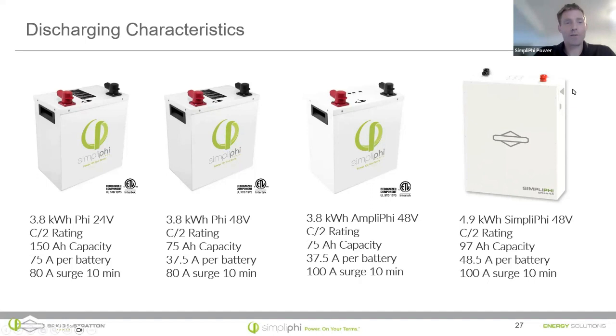Let's talk about discharging the batteries. On the discharge side of things, we can actually surge the batteries, so they're capable of discharging at higher amperages for shorter amounts of time. If I have a battery under standard temperature conditions like room temperature, I can pull 80 amps out of the Phi batteries, so 80 amps out of both the 24 volt and the 48 volt. So a C/2 discharge. If I'm going to do it continuously, I would want to use 75 amps per battery for the 24 volt and 37.5 amps for the 48 volt battery. But if I want to just pull a short amount of current out for a limited time, both of those batteries can surge to 80 amps.